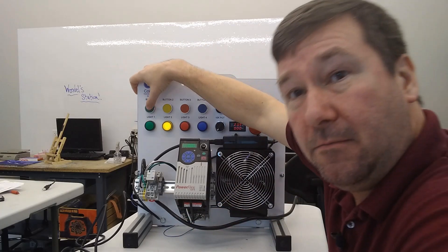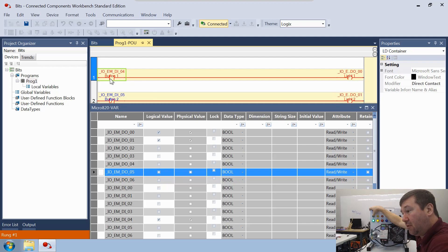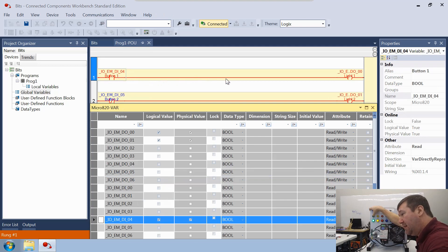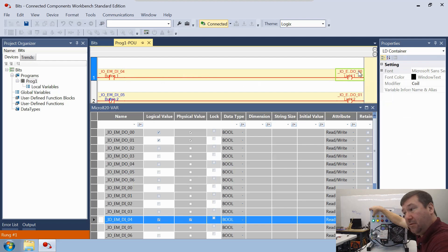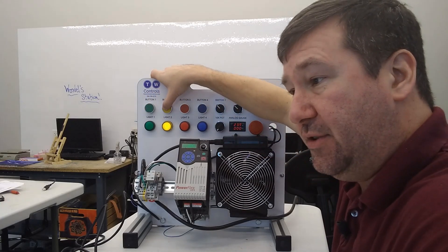So now let's press Button 1. We see the light come on — but how does it come on? We have a Direct Contact, which says go look for a 1 at Input 4. Do I have one? Yes — so this is going to be true, represented by the red. It's going to pass true conditions to this coil. And a true coil is going to say go write a 1. Where to? Output 0. And that is why the light is on.